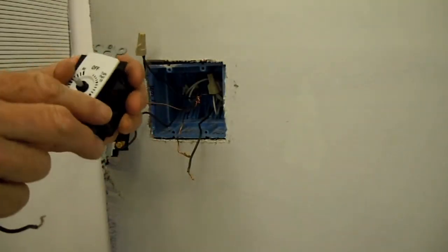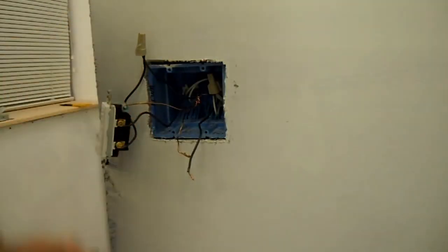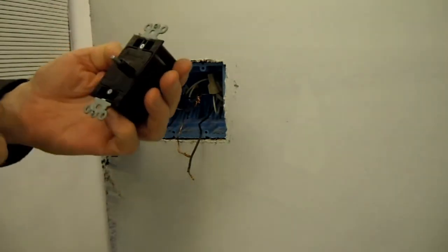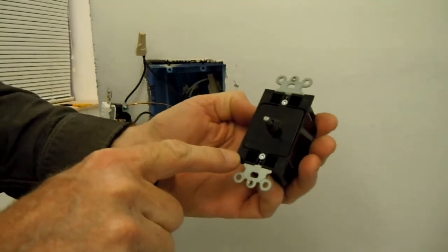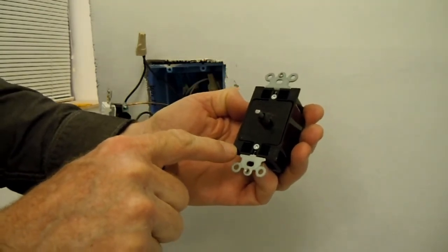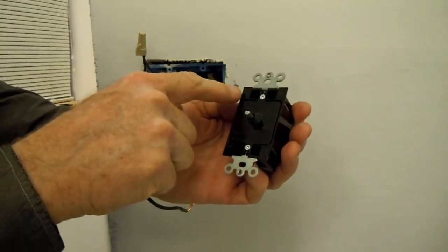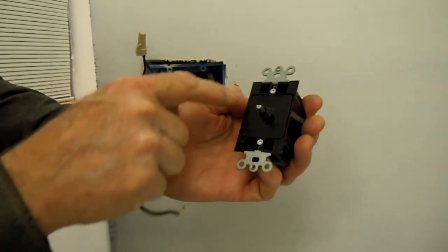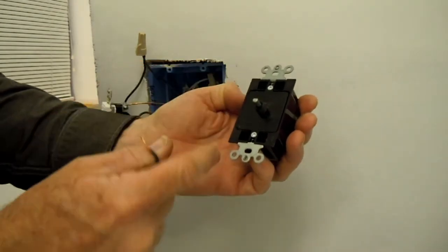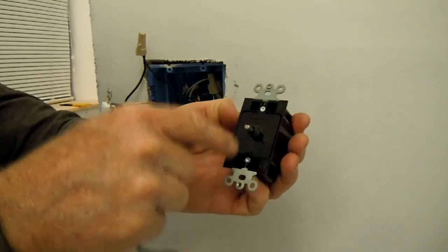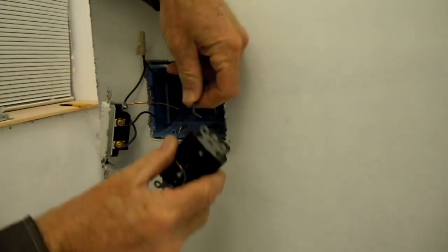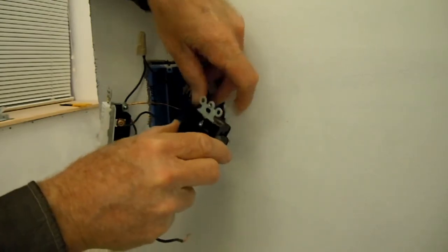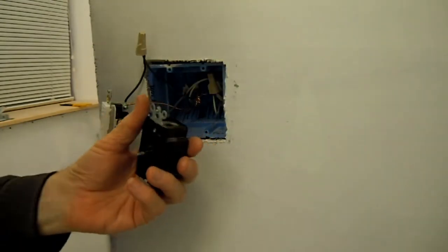Okay, now the same situation with this. What you need to do with these timers is look for the place where it says line and load. Here it says, I don't know if you can see that, but it says line and load. So line 1, load 1. I put the power to there and the switch leg to there. Here's our switch leg.